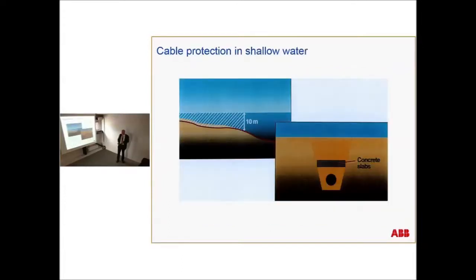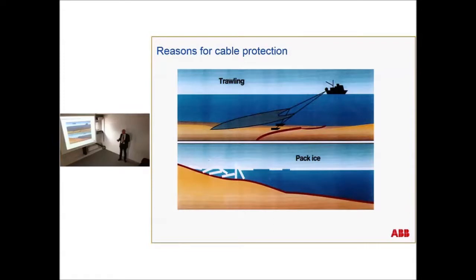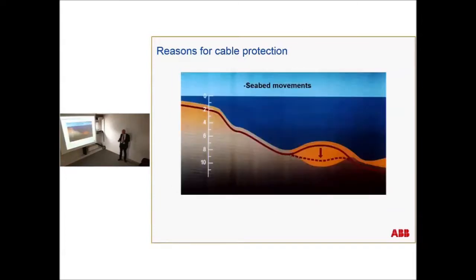In shallow water, it can be tricky if you have moving sand dunes under the seabed, because if you bury the cable and you have a lot of sand on the cable, then the thermal resistance will increase and you will need to reduce the ampacity of the cable. Sometimes you also need concrete slabs to keep the cable in place. The reason is, of course, if you have fishing activities, it should not affect the cable. If you have a lot of pack ice, it should not affect the cable. If you have seabed movements and the sand moves away, suddenly the cable is open in the sea. So there is very much to think of.